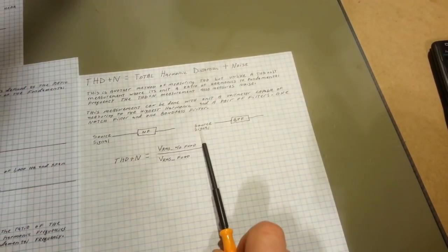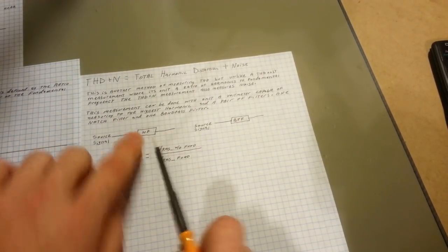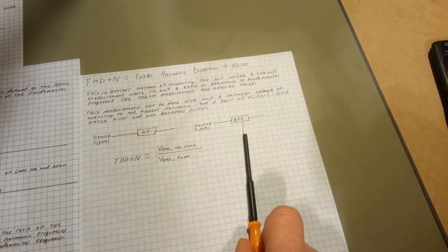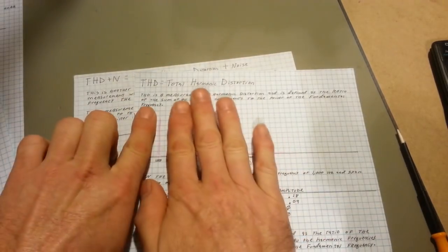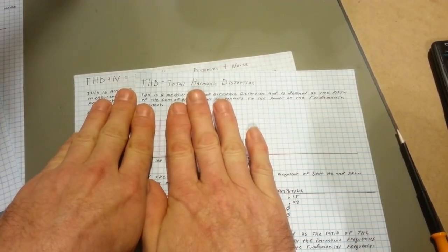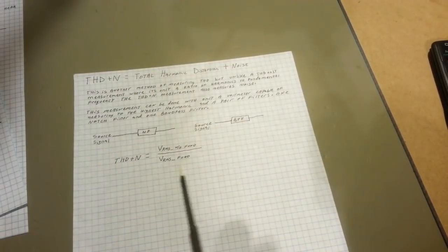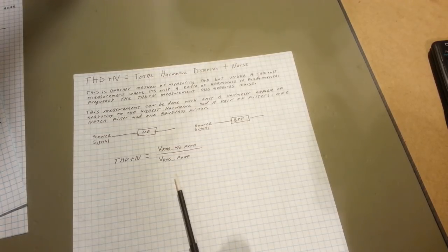It then also passes that same signal. After it takes that measurement, it passes it through a bandpass filter. Now the bandpass filter, the only thing it's going to measure is going to be the peak, because it's a band pass. It's only going to pass, let's say, that 1 kilohertz audio tone. And it's going to take another measurement. And that's going to be what's on the bottom of the formula here. And that's it. It's just 2 voltage measurements.